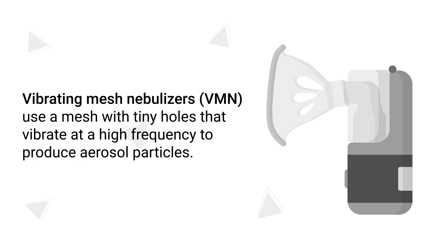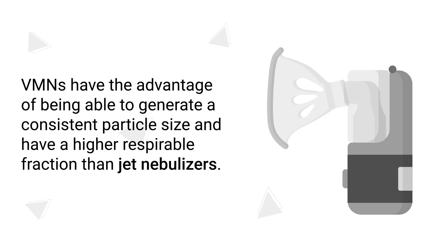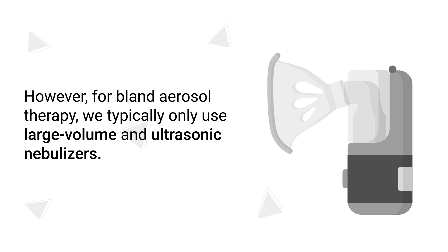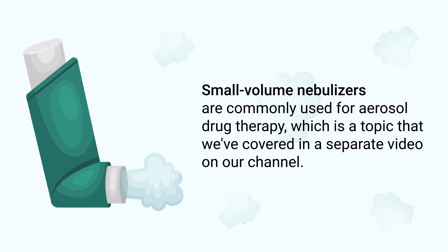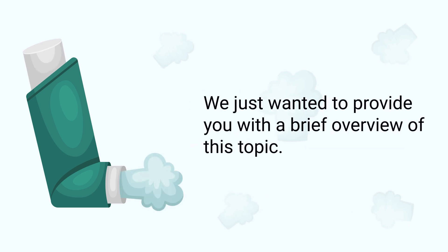Vibrating mesh nebulizers use a mesh with tiny holes that vibrate at a high frequency to produce aerosol particles. These have the advantage of generating a consistent particle size and have a higher respirable fraction than jet nebulizers. However, for bland aerosol therapy, we typically only use large volume and ultrasonic nebulizers. Small volume nebulizers are commonly used for aerosol drug therapy, which is covered in a separate video.